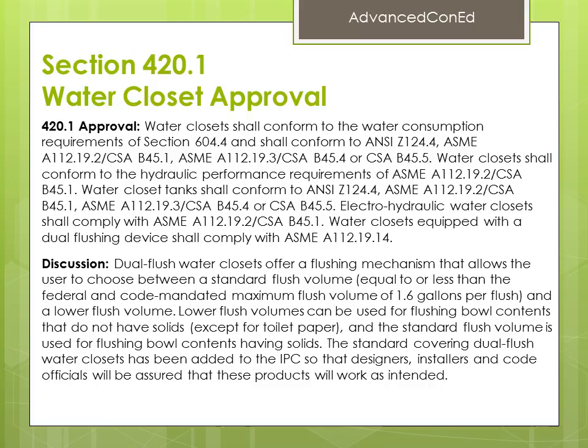Water closets shall conform to the hydraulic performance requirements of ASME A112.19.2, CSA B45.1. Water closet tanks shall conform to ANSI Z124.4, ASME A112.19.2, CSA B45.1, ASME A112.19.3, CSA B45.4, or CSA B45.5.